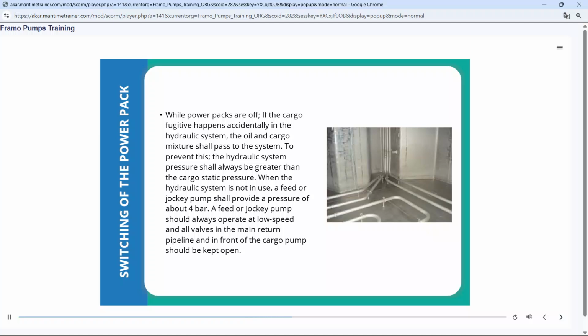When the hydraulic system is not in use, a feed or jockey pump shall provide a pressure of about 4 bar. A feed or jockey pump should always operate at low speed, and all valves in the main return pipeline and in front of the cargo pump should be kept open.